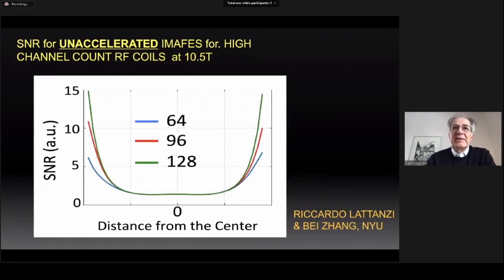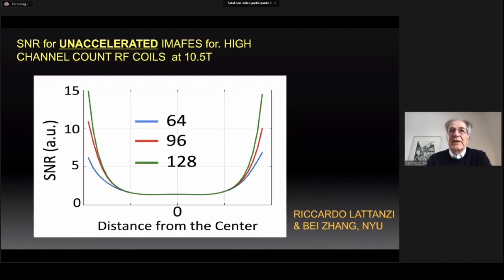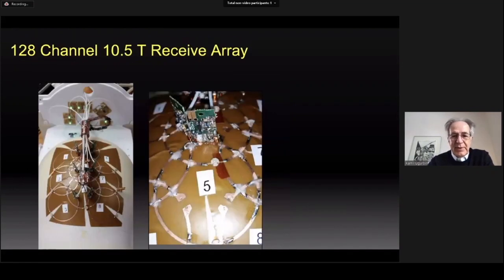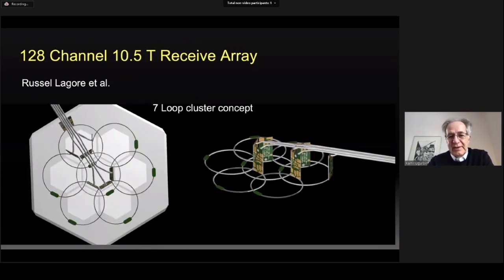We expect even higher gains with 128 channels. For unaccelerated imaging, the gains will be mainly peripheral as shown in simulations here, but for accelerated imaging — which is the real acquisition condition — the gains will be over the whole brain. Therefore, having completed the 64-channel coil, we are now working on 128-channel coil development. Here are some progress reports: a section of the coil cluster with our homemade on-coil preamplifiers, and a schematic drawing showing the amplifiers and coils together. Such clusters will be tiled to achieve the 128-channel coil.